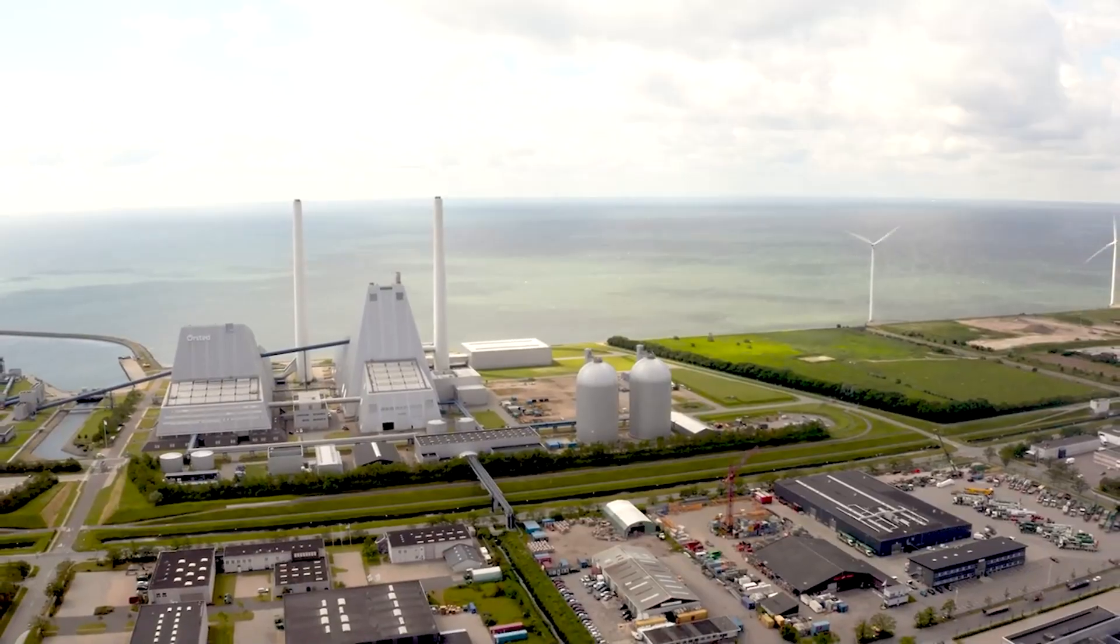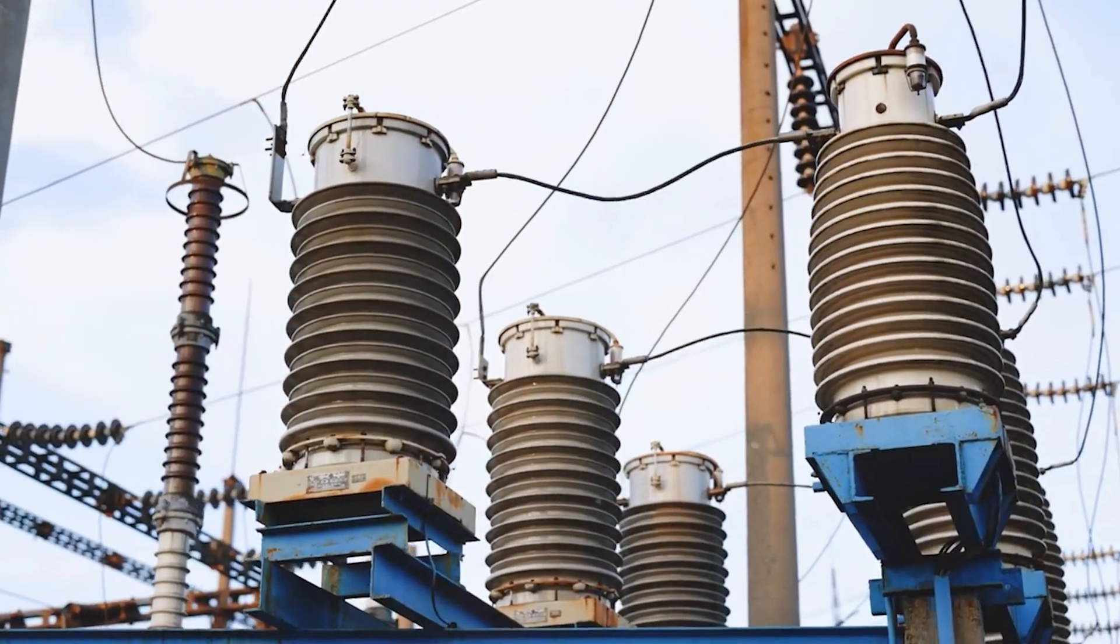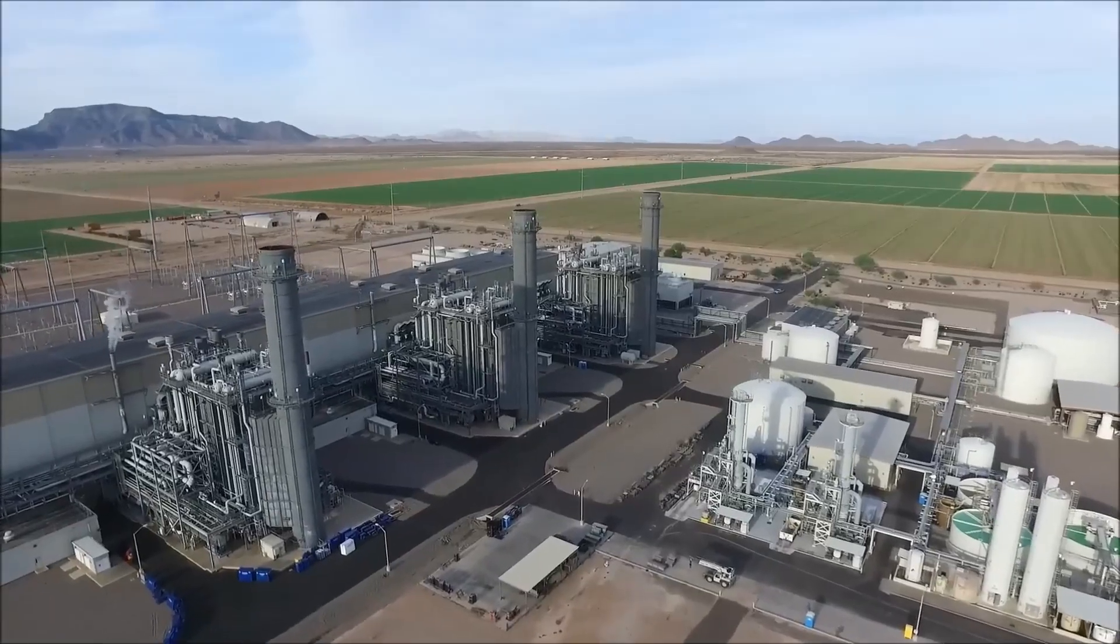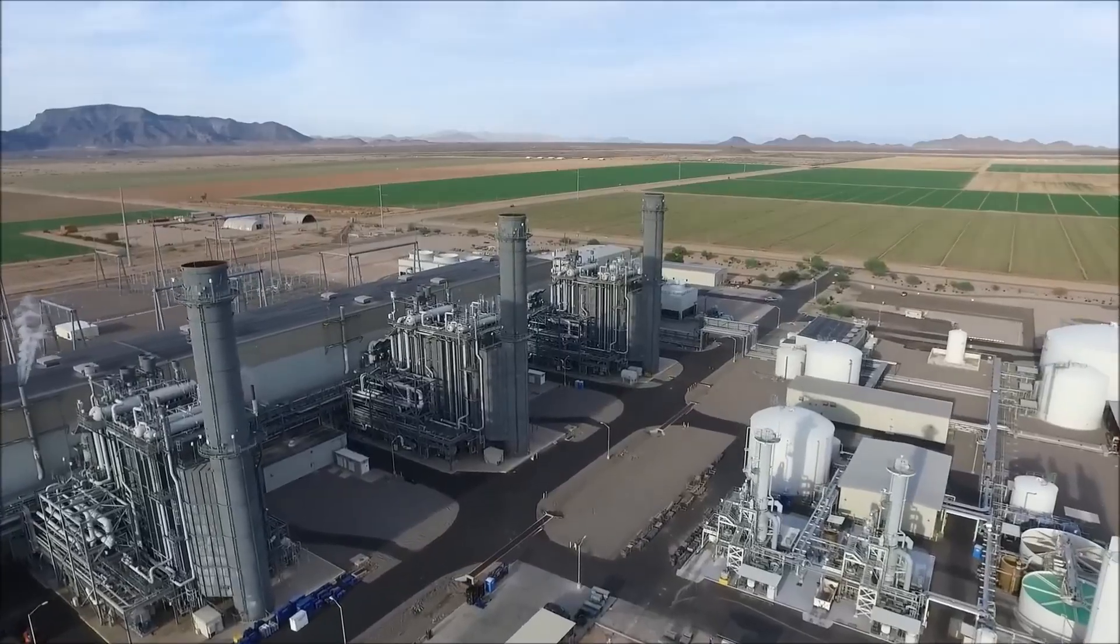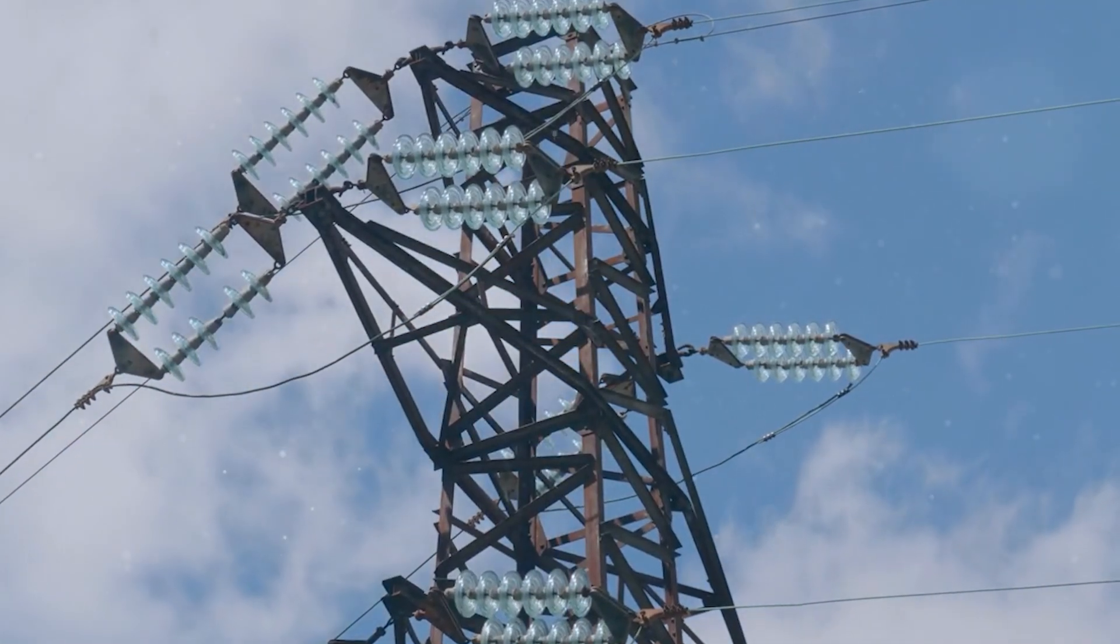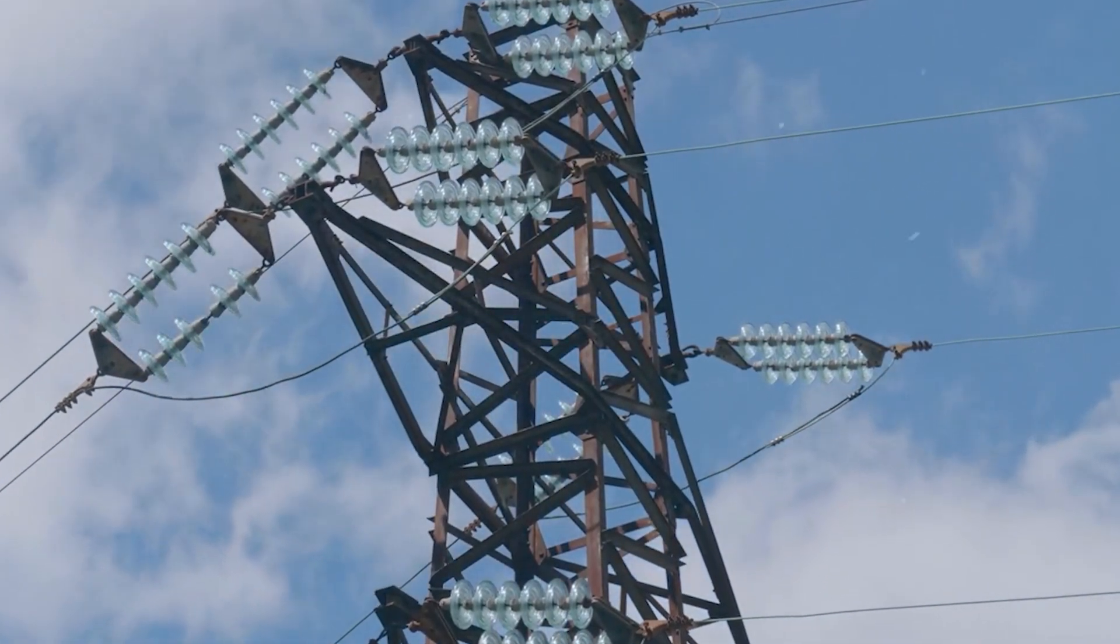The sudden drop in production from these solar facilities caused the system frequency to dip to 59.7 hertz, a point dangerously close to triggering an emergency response. The loss of so much generation capacity in such a short time could have required rolling blackouts to bring demand and supply back into balance.